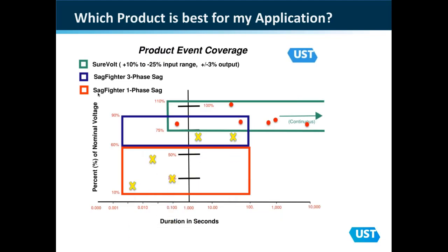And again, here's this chart that we use to separate the two products, just to circle back. The voltage regulator is going to continuously monitor and make tap changes to make corrections for voltage. The Sag Fighter is going to sit in standby, waiting for a sag to occur. The Sag Fighter can correct for deeper voltage events.